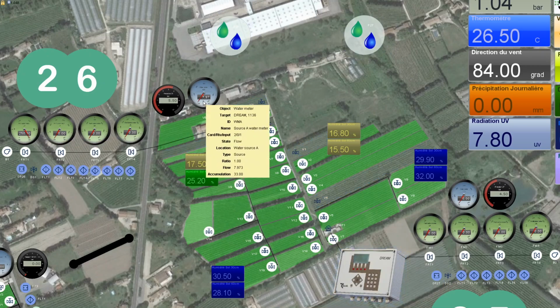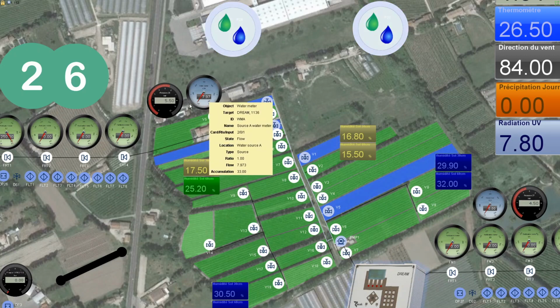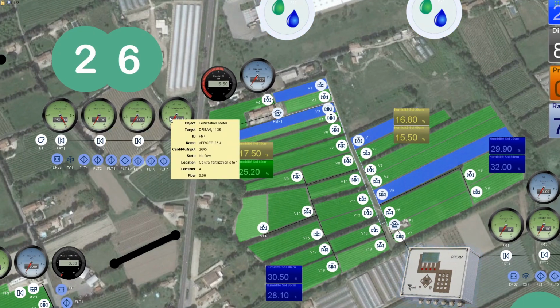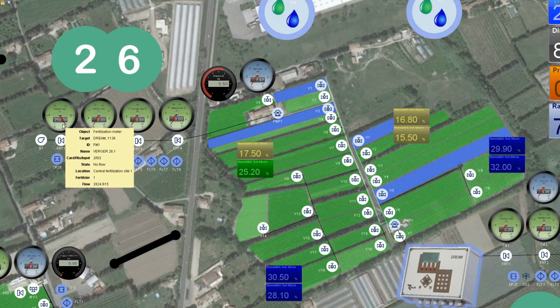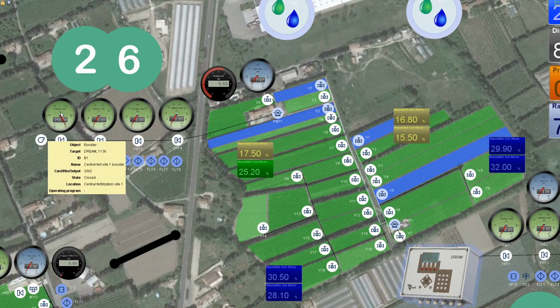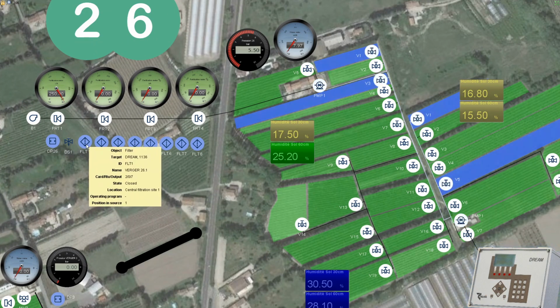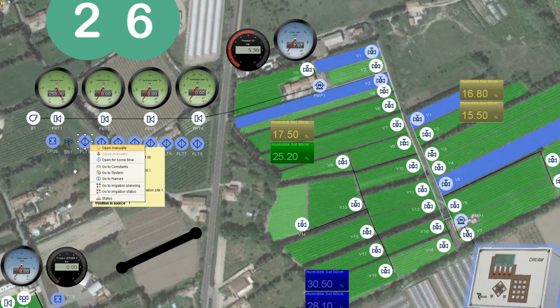We can see other things here. There's a flow meter currently showing 7.97 cubic meters per hour. There's a pressure sensor showing 5.5 bar. There is a third bench made of 4 injectors showing 250 liters of injection on FET number 1. There is a booster on this particular third bench. We can also see some icons representing the filters. There's a modular filtration system with 8 pods, from filter 1 to filter 8. Those icons represent the backflush valves, where we can manually backflush each pod instead of running it automatically like it should be.